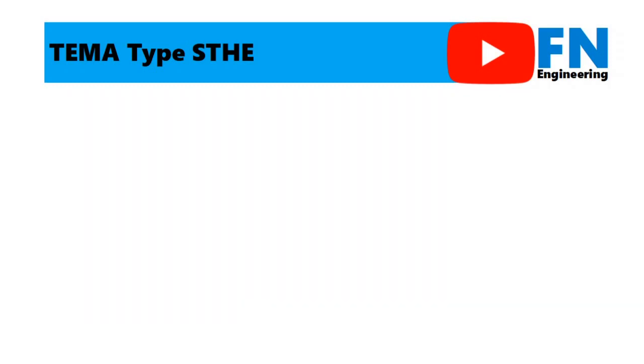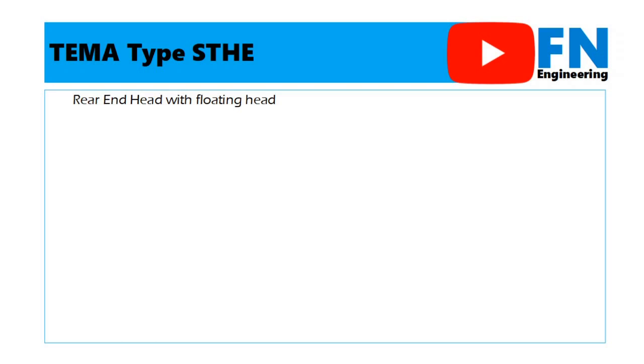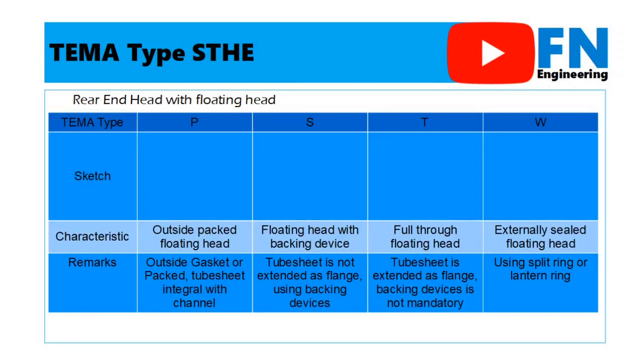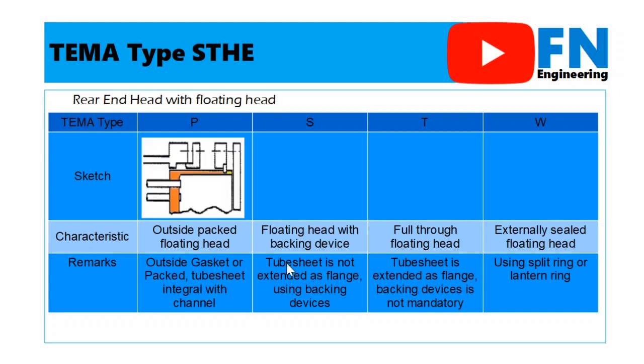The last is the rear head configuration with a floating head. There are four types of floating heads, namely type P, type S, type T, and type W. Next, we are going to know these types in more detail. We have to see the picture carefully. Type P is an outside packed floating head. It means we use a flange bolting connection on two sides. There are shell side and channel side. Moreover, the tubesheet is integral with the channel.